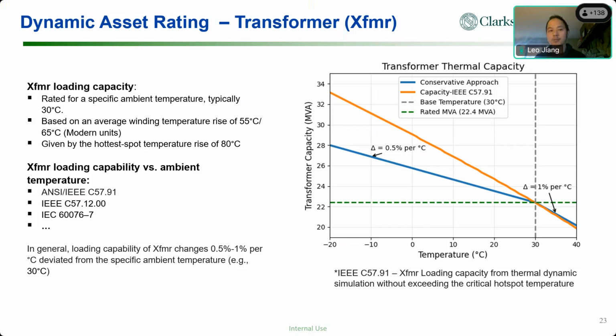One of the aspects we are trying to see there is, what is the rating of the asset? For example, for the transformers, if you look at the nameplate for the transformers, look at the manufacturers there, the transformer rating is designed, the number is provided or given under certain conditions. For example, transformers in general are rated for a specific ambient temperature, typically 30 C.